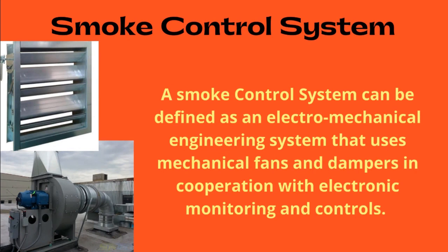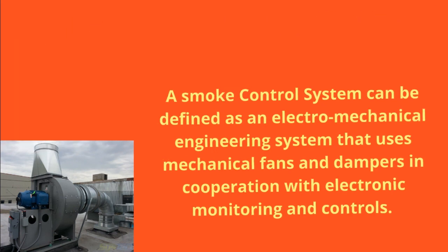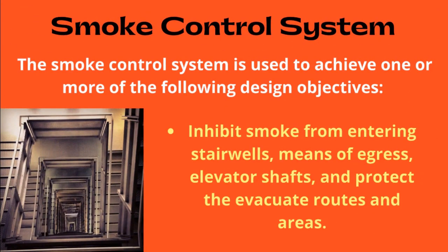A smoke control system can be defined as an electromechanical engineering system that uses mechanical fans and dampers in cooperation with electronic monitoring and controls. The system produces pressure differences across smoke barriers that inhibit or facilitate smoke movement. The smoke control system is used to achieve design objectives such as inhibiting smoke from entering stairwells, means of egress, elevator shafts, and protecting evacuation routes and areas.